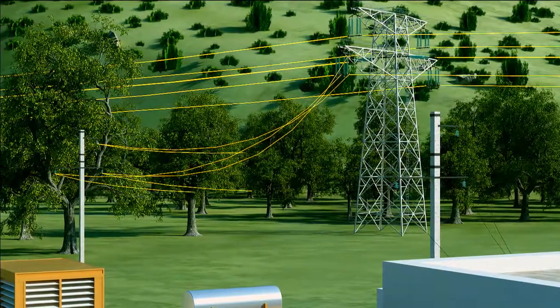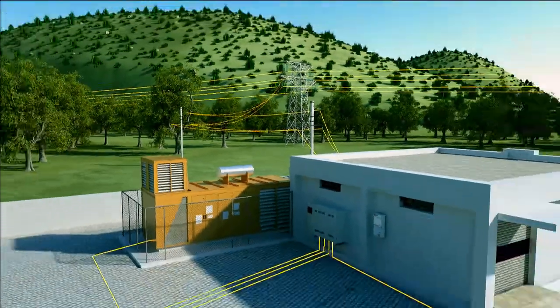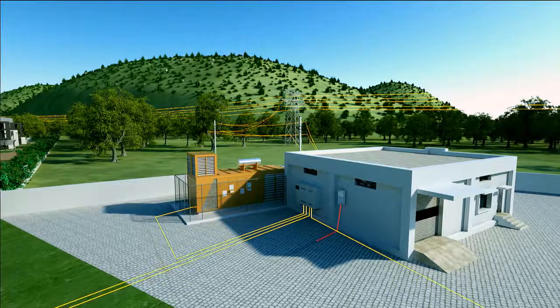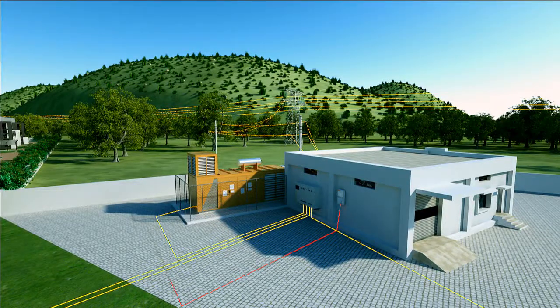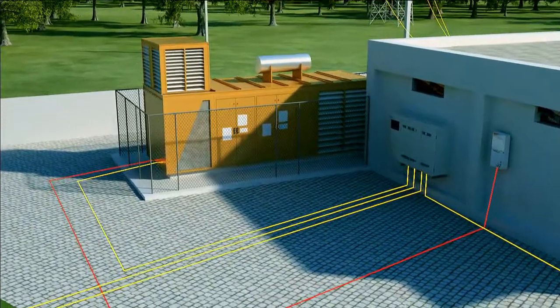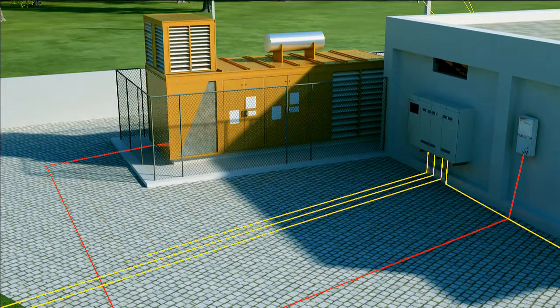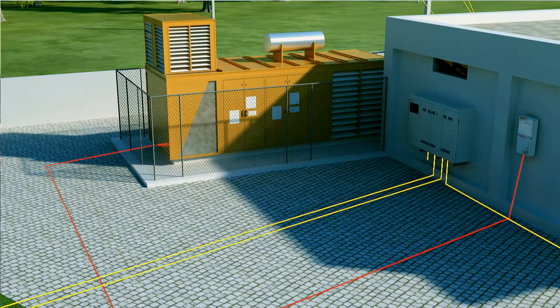When MAX detects availability of grid, it turns off the diesel generator and restores power to the plant using the grid. Inverters come in synchronization with grid power and continue normal operation.